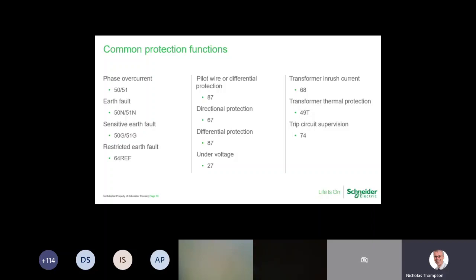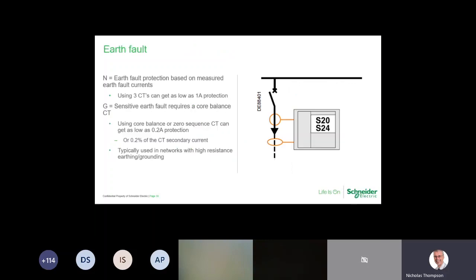And then transformer inrush current, you can have that on the protection relay. You can also do thermal protection on your relay, and this is by calculation. It's not measured, it's by calculation. And I mentioned trip circuit supervision. This is functionality within the relay, but it's also a simple relay, which can be working in parallel with the actual main relay.